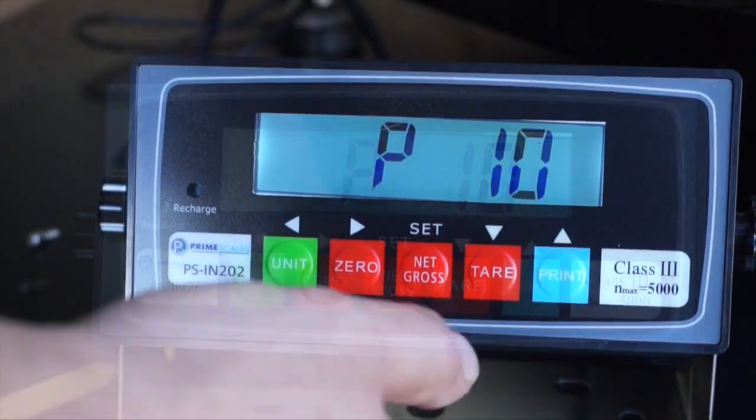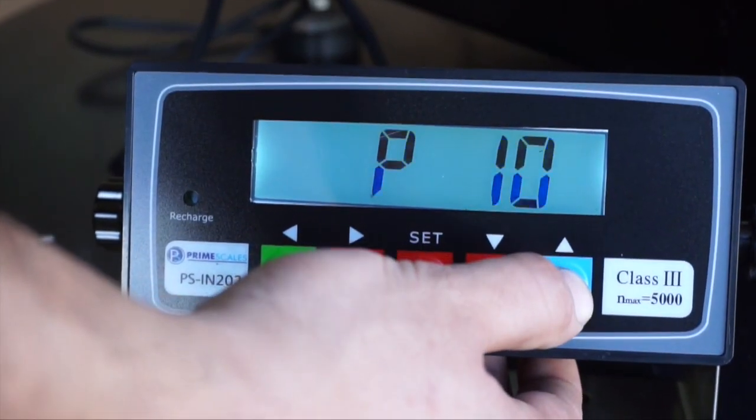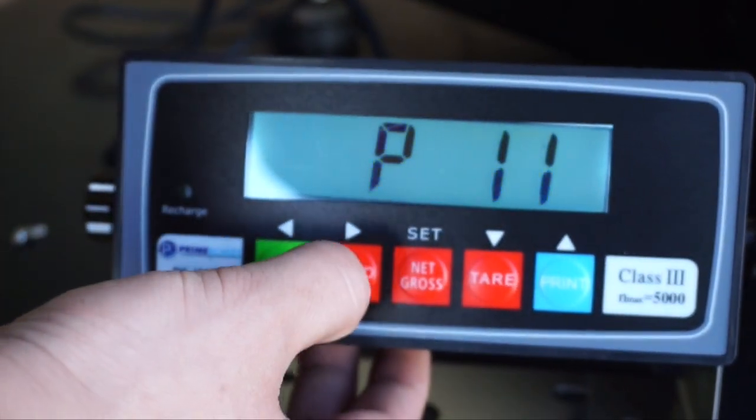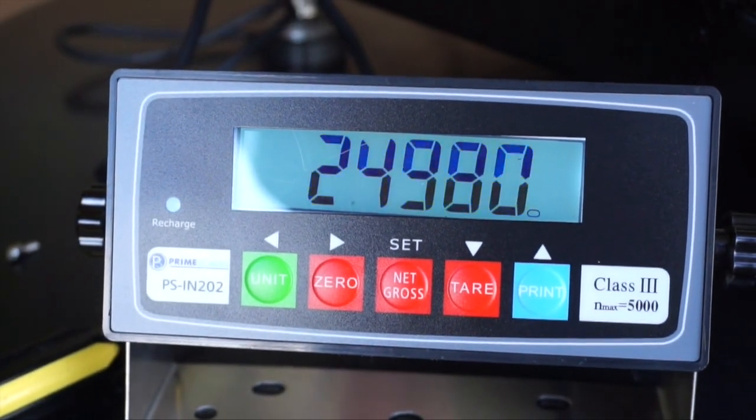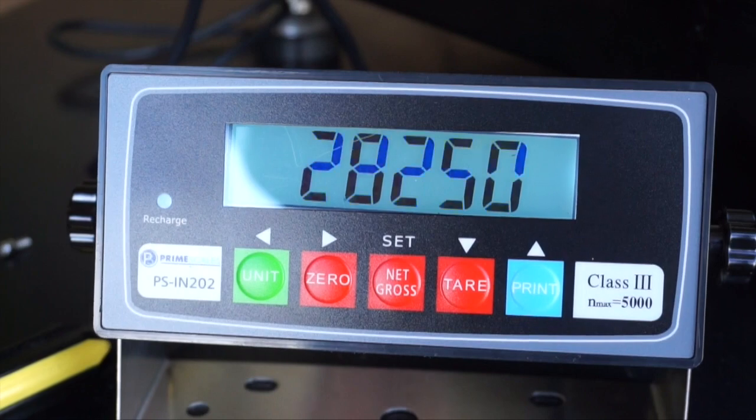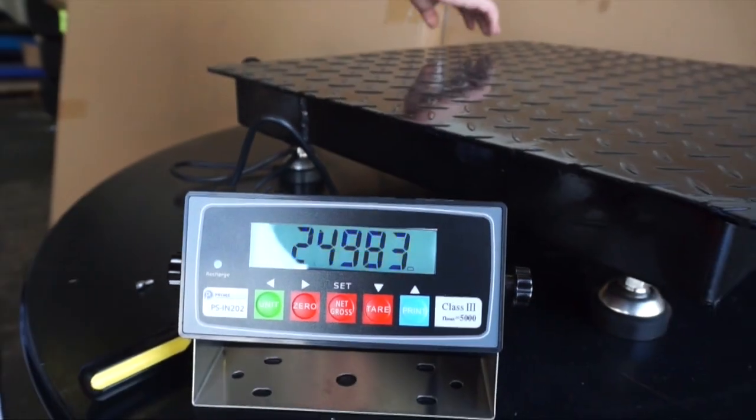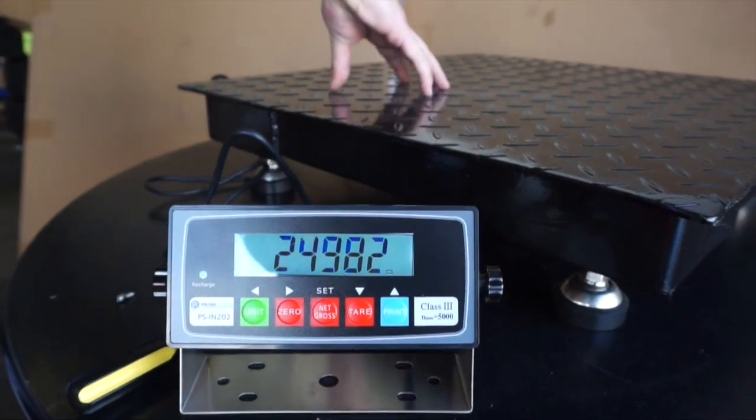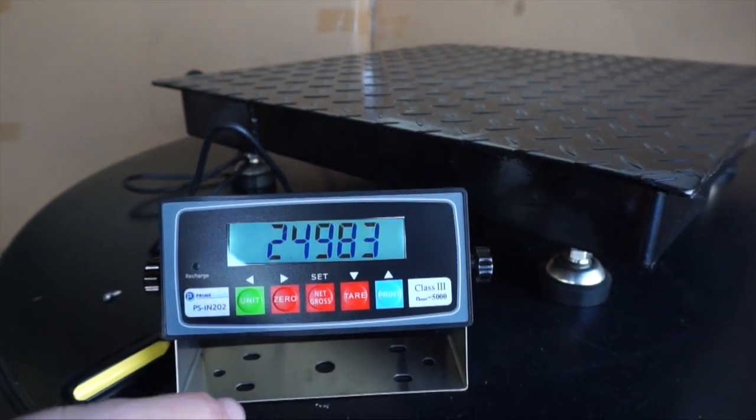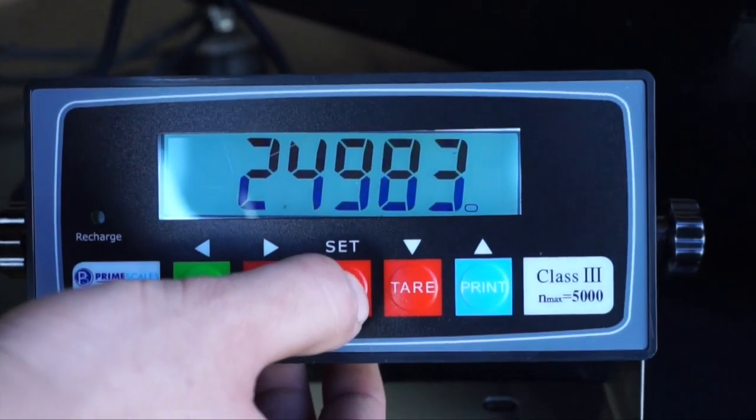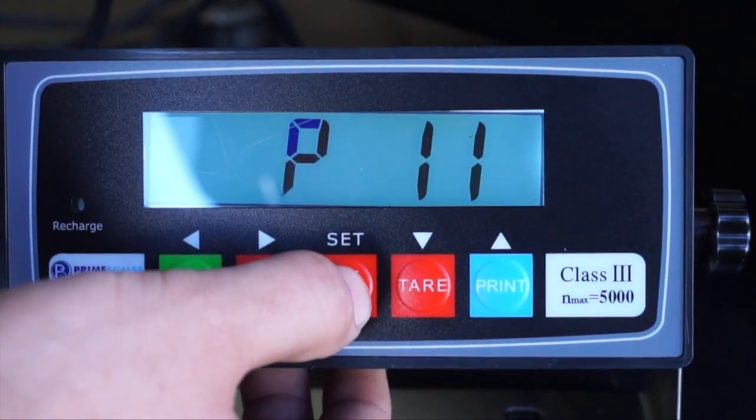Move up to P11 with the print button and press zero to enter. P11 is internal reading of the scale. Numbers should change when pressure or weight is added on the scale. After confirmation of live internal reading, wait for the numbers to stabilize and press net gross. You will automatically come out to parameter 11 or P11.